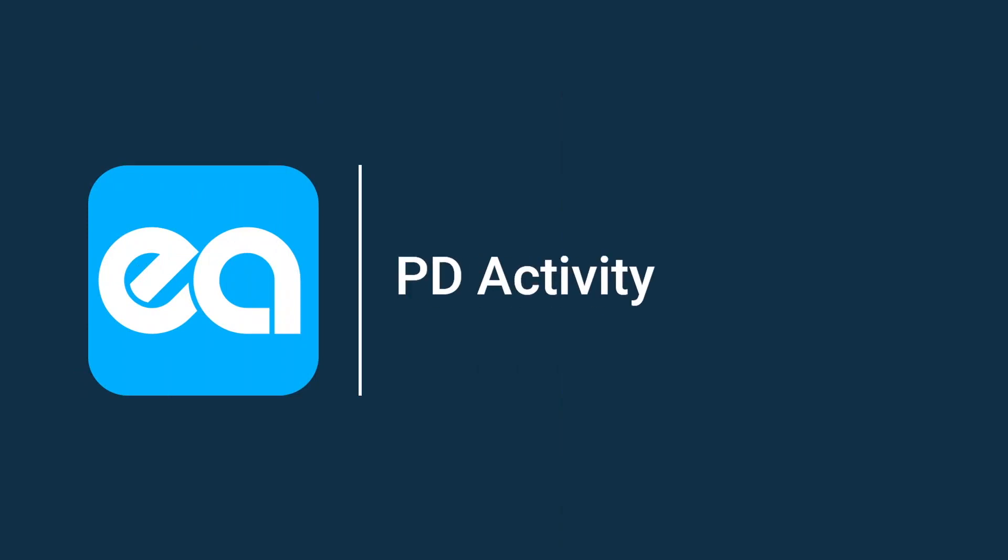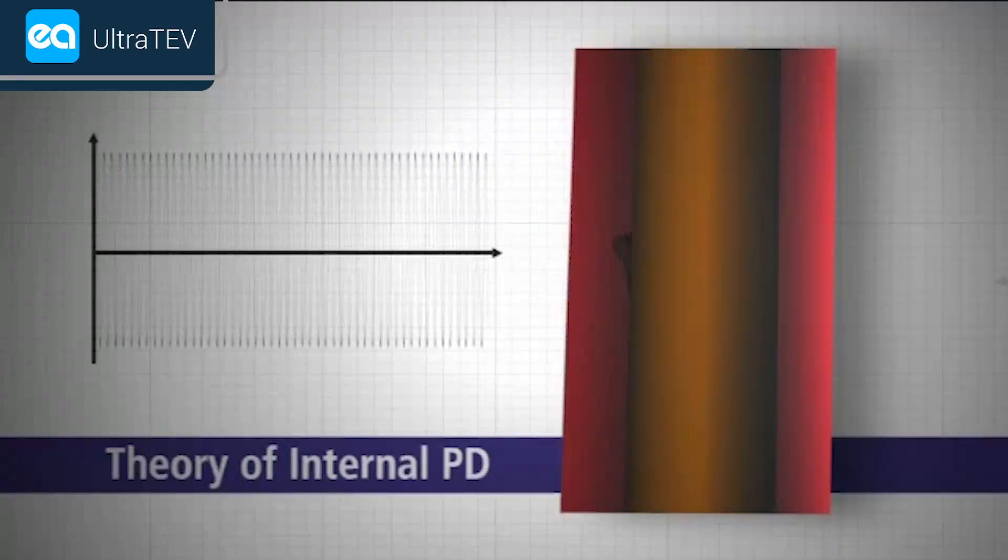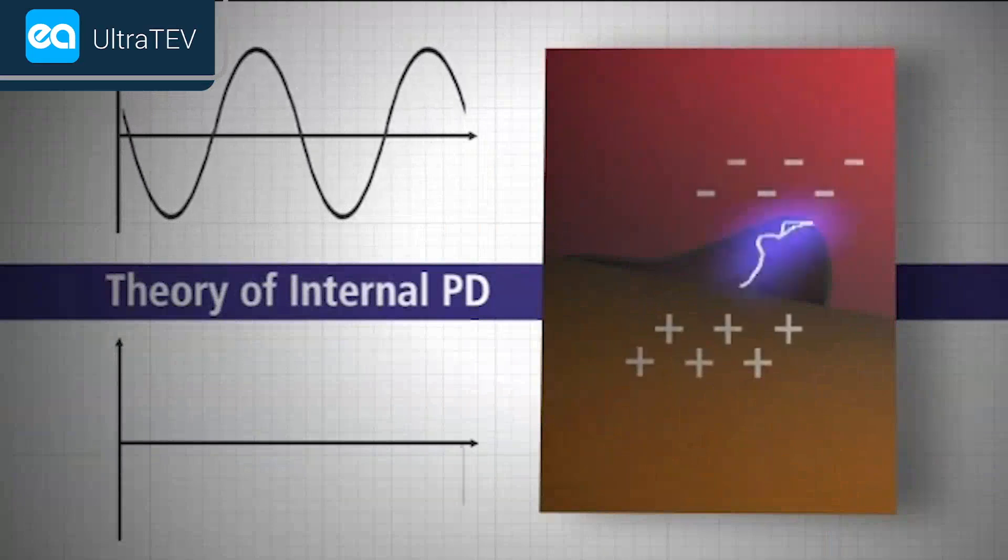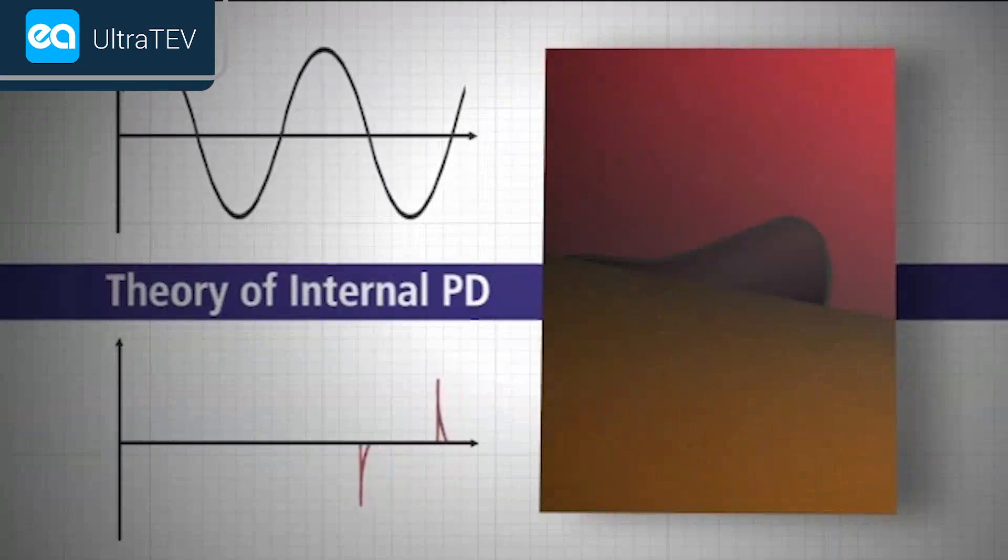PD activity can occur at any point in the insulation system where the electric field strength exceeds the breakdown strength of that portion of the insulating material.